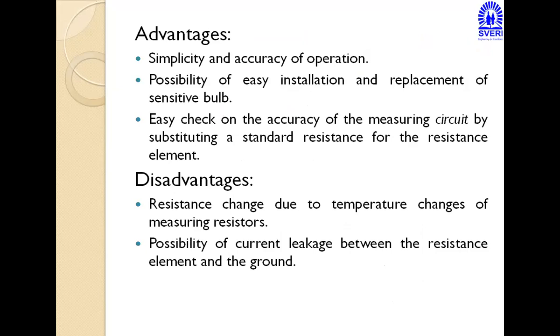Second, possibility of easy installation and replacement of sensitive bulbs, means you can use the laboratory type and industry type resistance. Third, easy check on the accuracy of the measuring circuit by substituting a standard resistance for the resistance element.